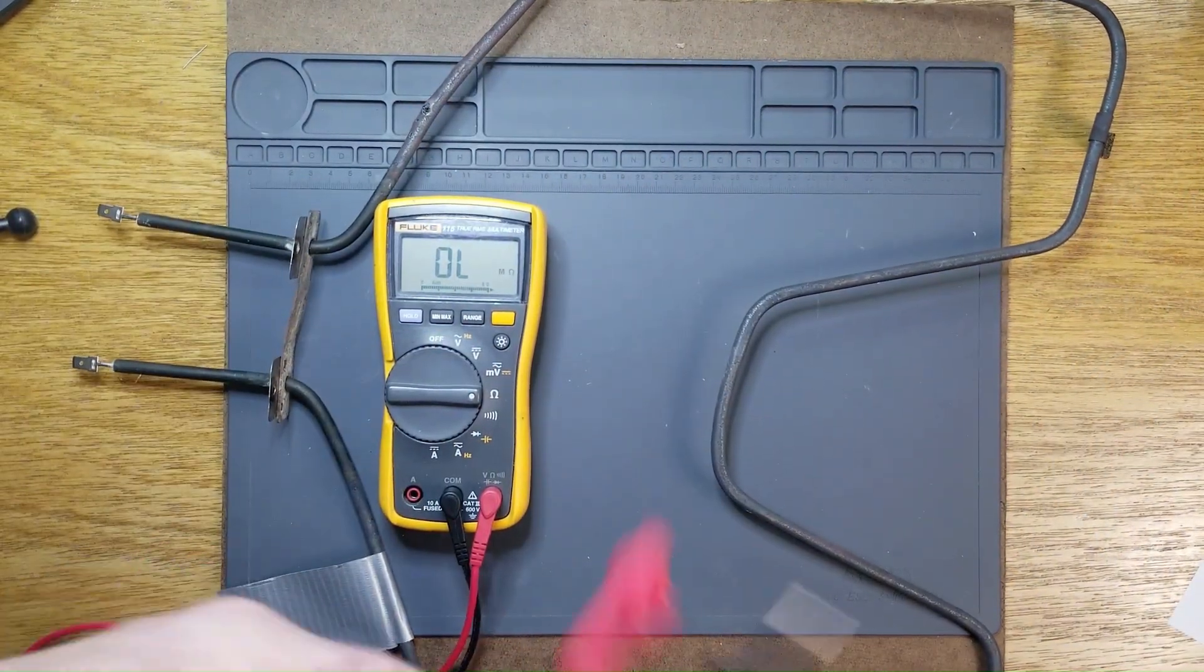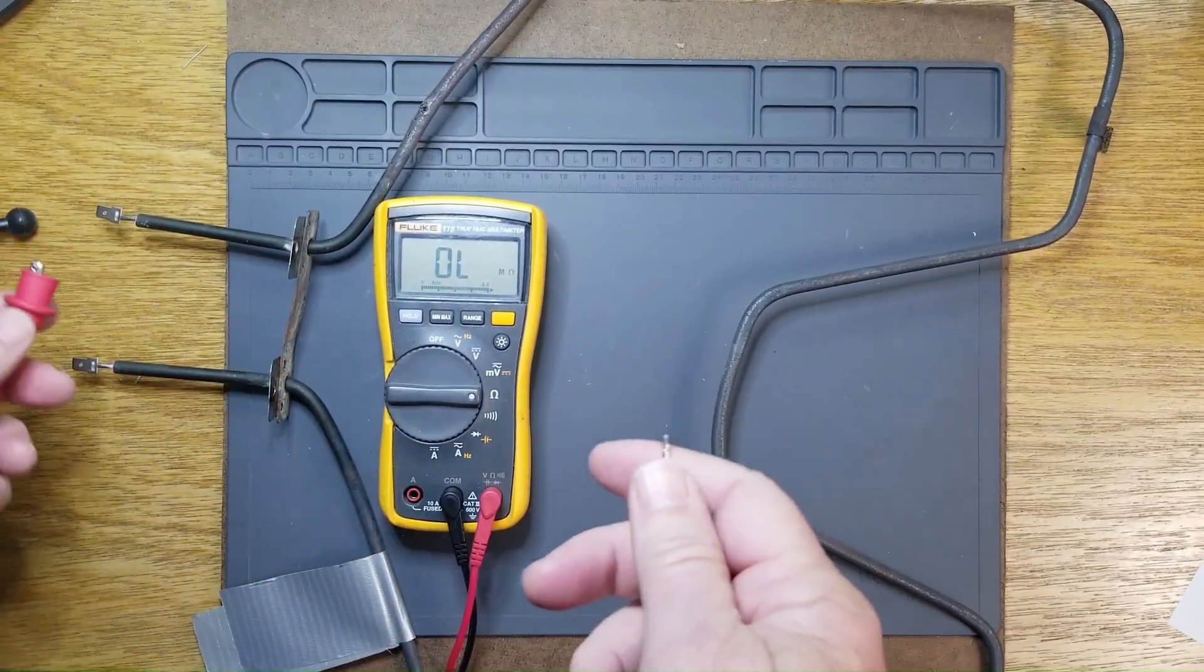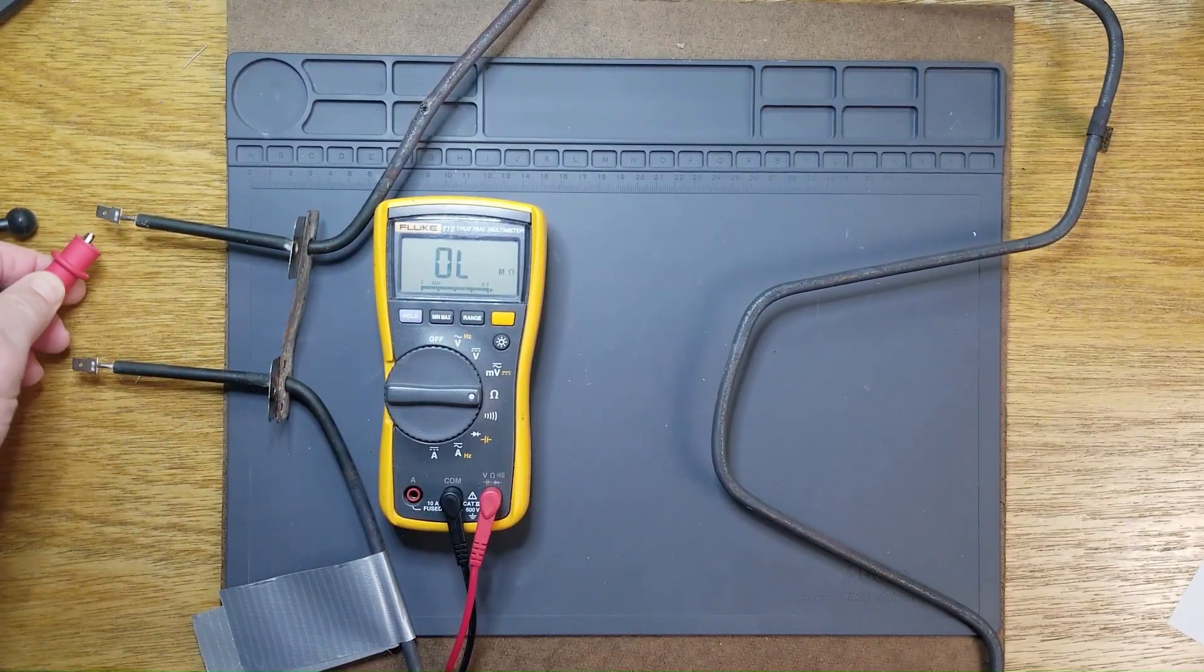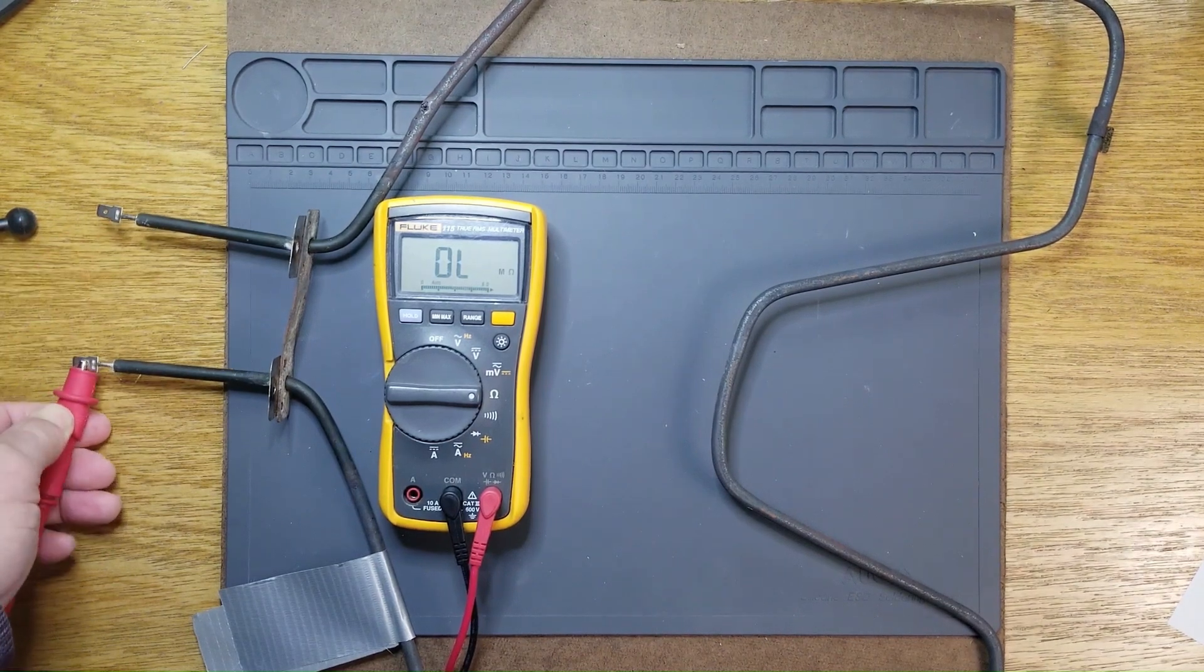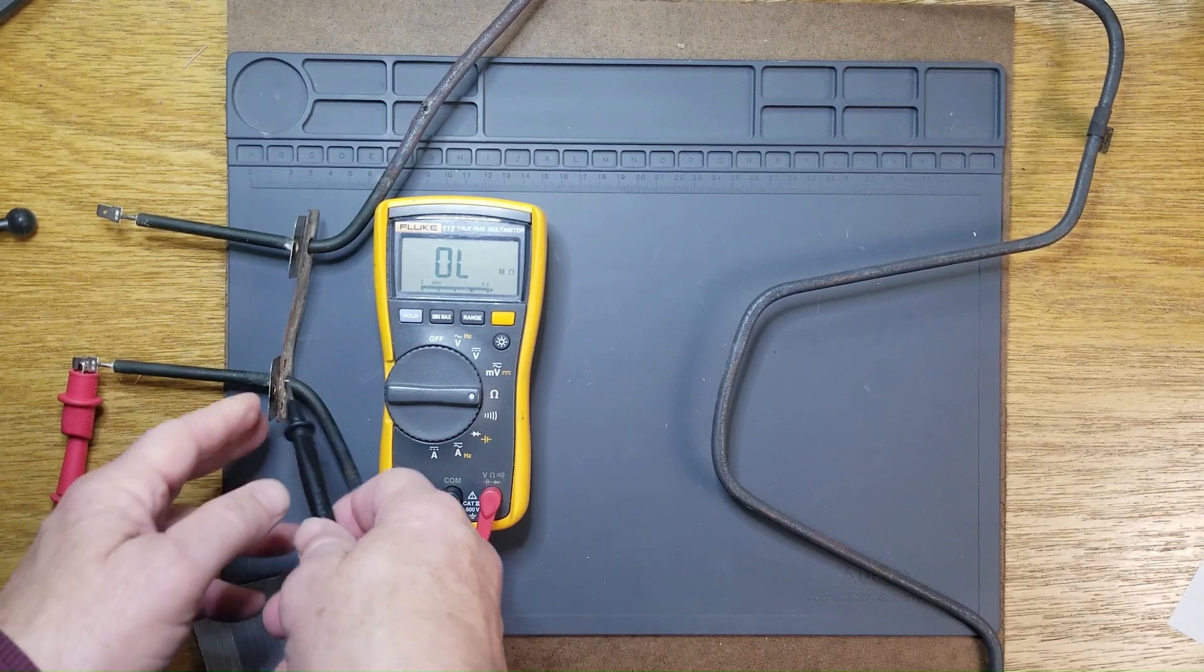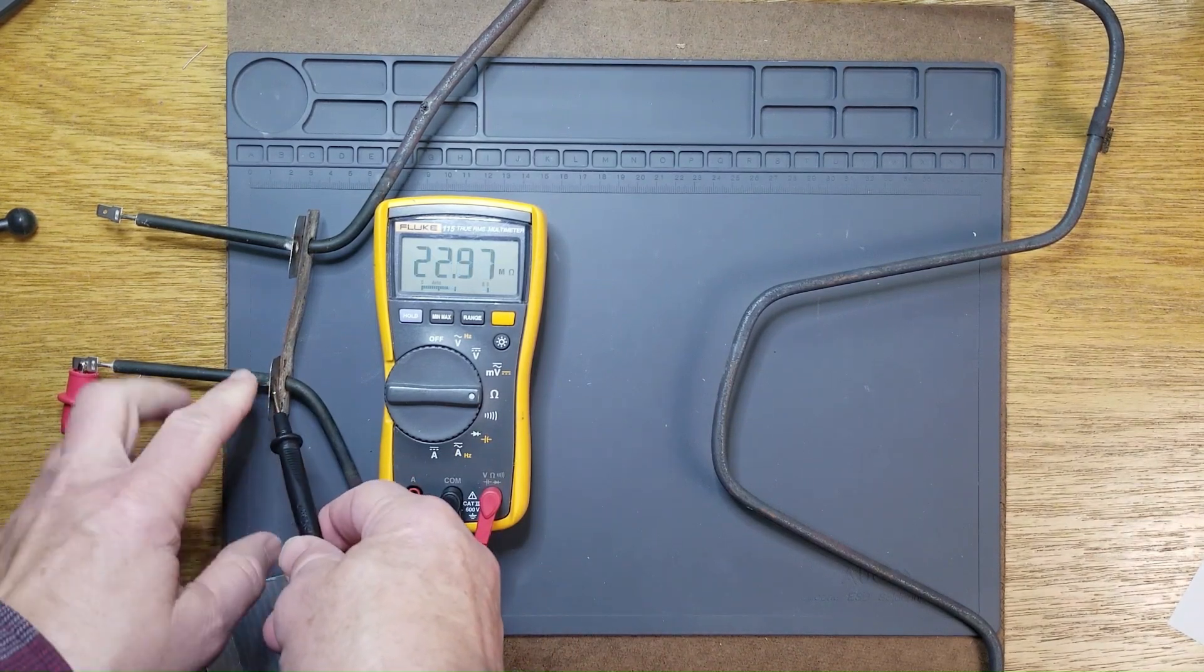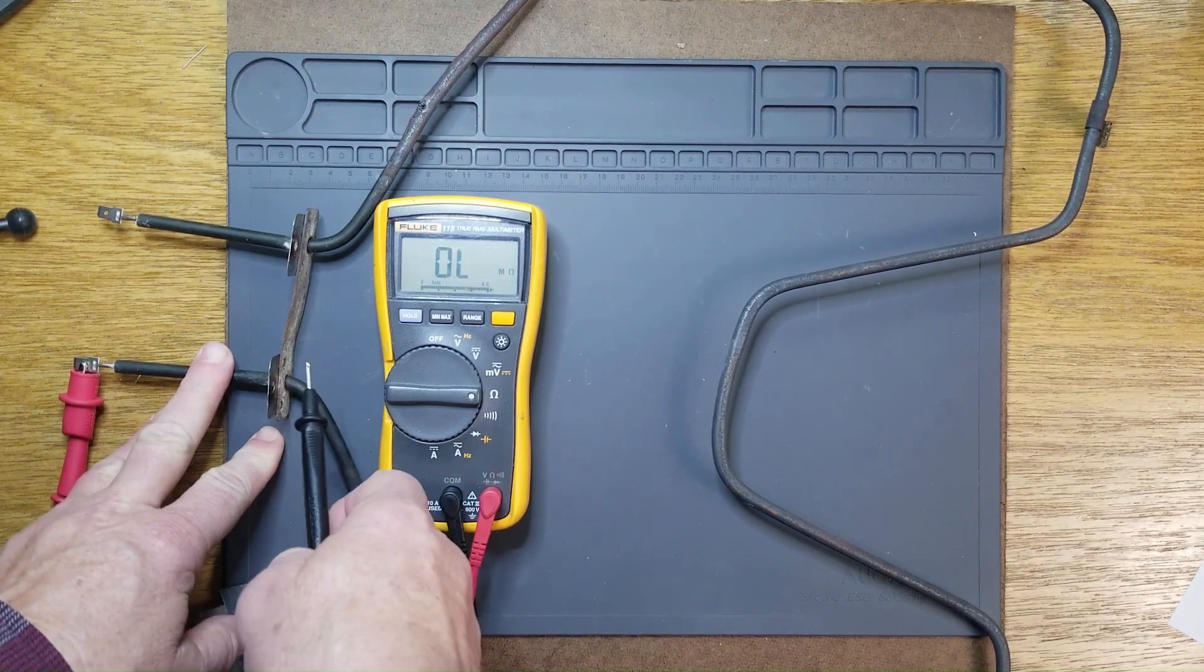However, when I measure and the key measurement here is why it was tripping the breaker is doing a resistance check to ground. However, when I do that resistance check, I was getting in the 20 megaohms range, which tells me there is something wrong.